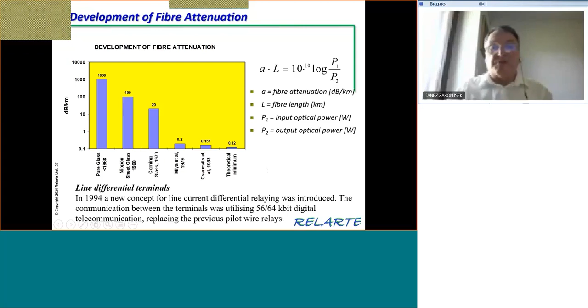Going back a bit to relay protection: in '94, rather late, line current differential protection was designed using direct optical fiber digital communication. That was an extremely big move from previous pilot wire relays to differential protection based on optical fiber communication.